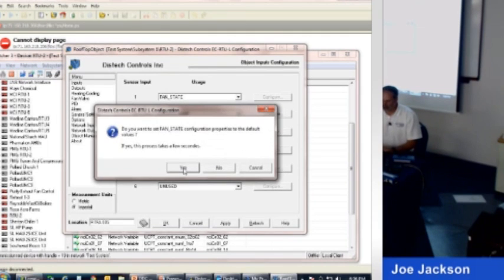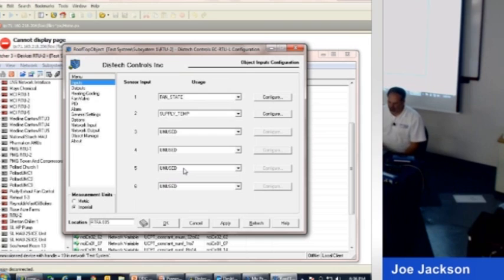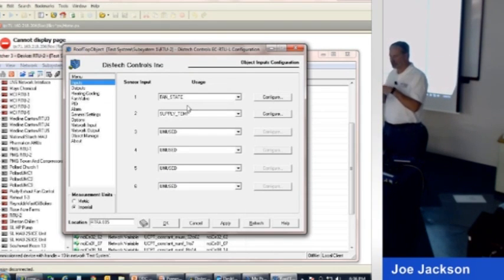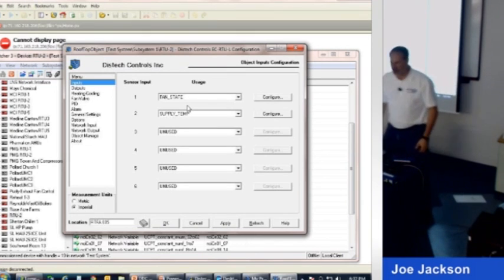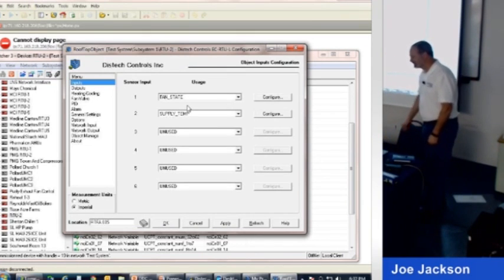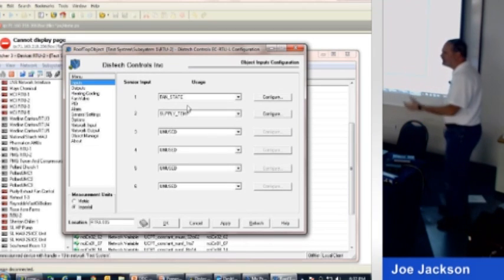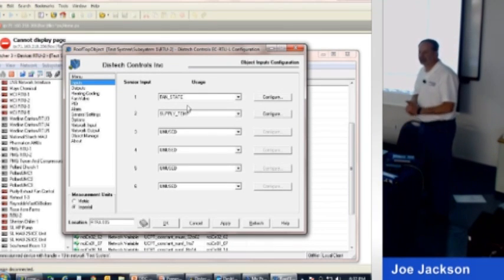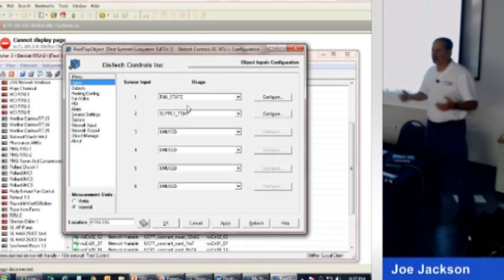We come down through here, and here are all my choices. Fan state. And it asks me a question if I want to set it up to the default, and I just say yes, and it's done. So this input is designed to have a little current sensing donut hung across the fan coil, fan wire, and when the fan current starts drawing, it catches it and tells us that the fan is running. Unfortunately, if it's got a belt on it, it may or may not tell you the belt's broke. So the status of the fan is definitely one choice. What else does every other rooftop have to have?